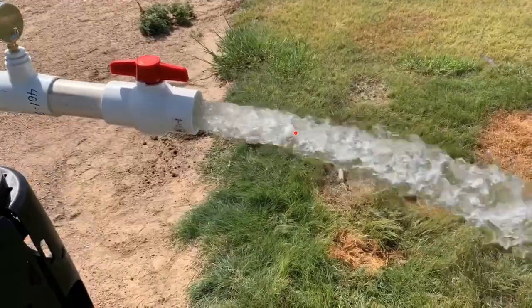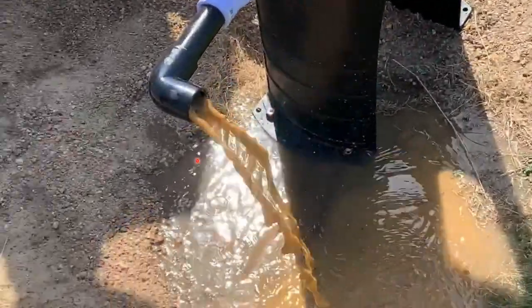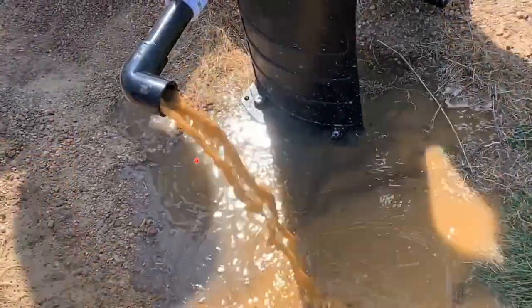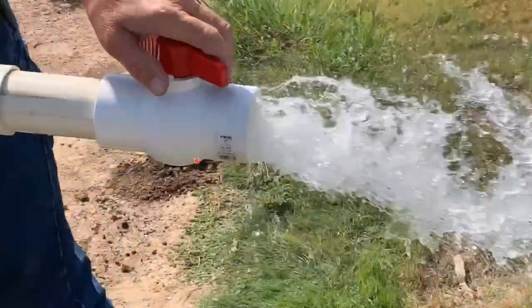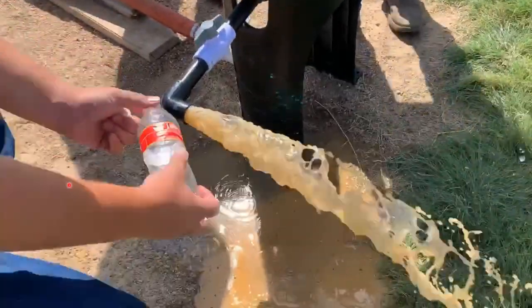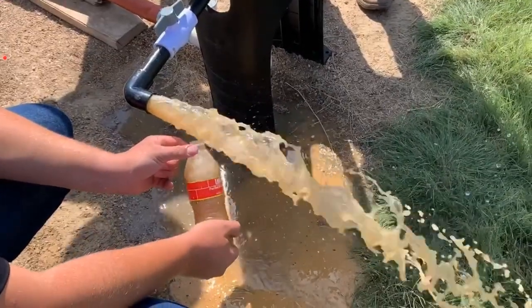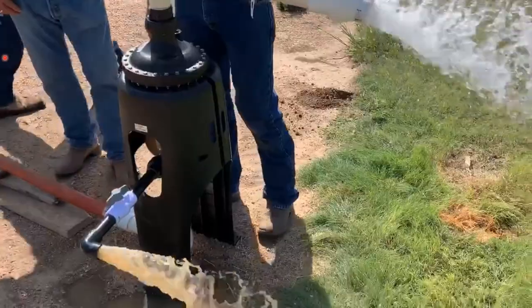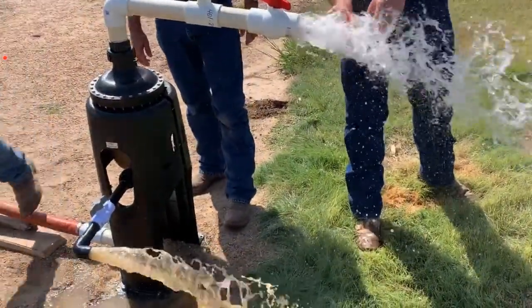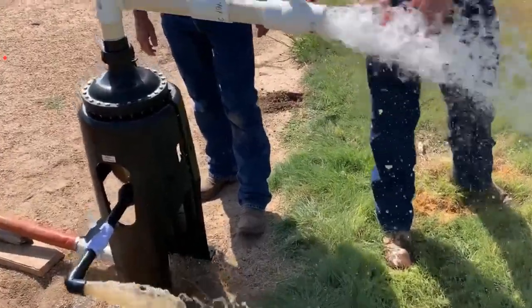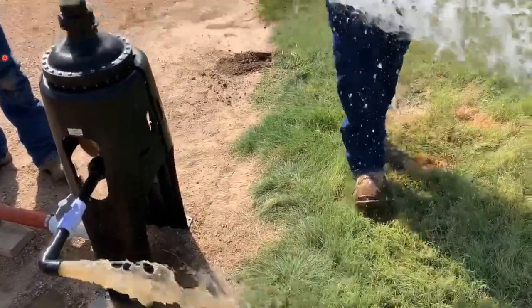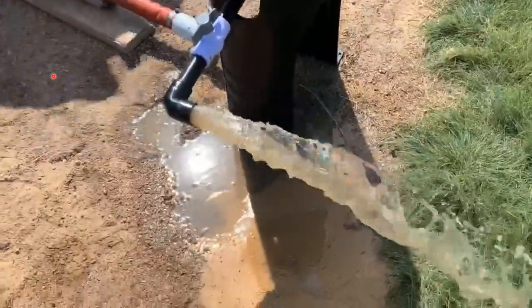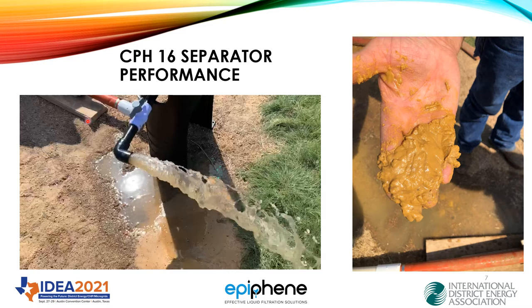And then as we move up, you'll see that I have clear water coming out. Normally we'd have an automatic purge valve on this, but in this case we wanted to show the comparison between the purges. Now he's basically closing it down, so we've got about a 3 psi differential across the separator. You can see it's still very efficient in removing the silt. So those two samples we took, we used those for our comparison between the outlet and the purge — actually it was 48 hours, but we used 24 hours to be conservative for our settling test.